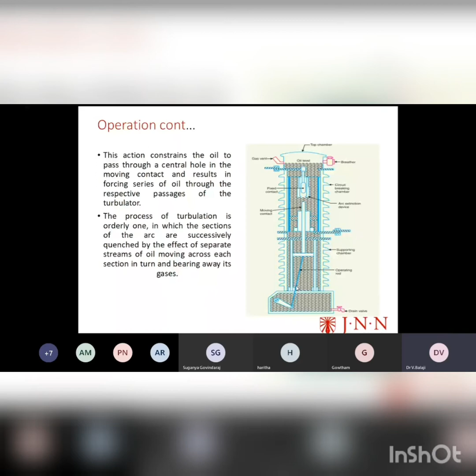That's why they are saying the process of turbulation is one in which the sections of the arc are successively quenched by the effect of separate streams. Some pressurized oil will be flowing across each sector in turn, bringing away its gases, bubbles hit the arc, and the arc will be quenched. So this is how the minimum oil circuit breaker works.